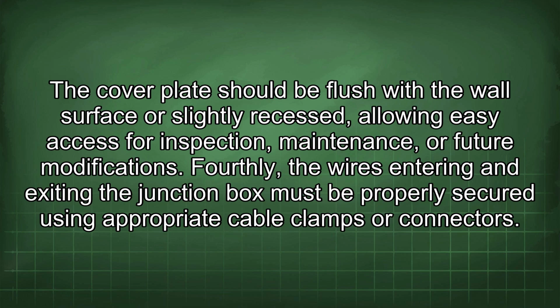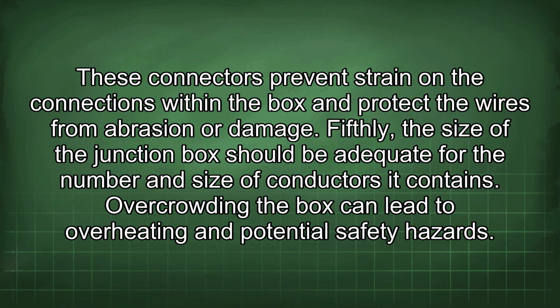Fourthly, the wires entering and exiting the junction box must be properly secured using appropriate cable clamps or connectors. These connectors prevent strain on the connections within the box and protect the wires from abrasion or damage. Fifthly, the size of the junction box should be adequate for the number and size of conductors it contains. Overcrowding the box can lead to overheating and potential safety hazards.